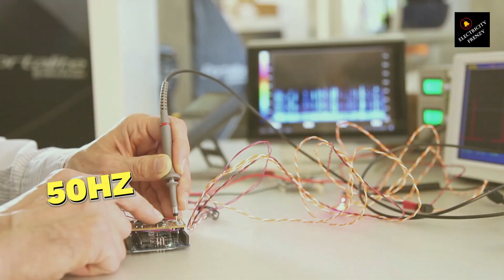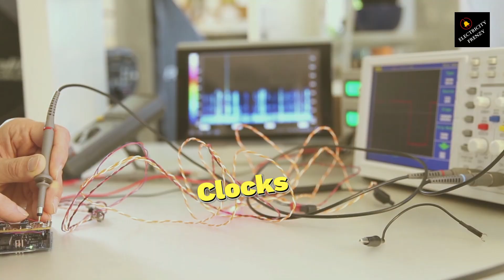Second case: different frequencies, 50 Hz versus 60 Hz. This is trickier, for example if your power supply is 50 Hz but your 110 volt appliance was designed for 60 Hz, or vice versa. This mismatch can create problems, especially with appliances that have motors, timers, or clocks. When the frequency is different, motors might not run properly. For instance, a motor designed for 60 Hz running on 50 Hz might run slower, heat up more, and wear out faster, because motors depend on frequency to operate at the correct speed.